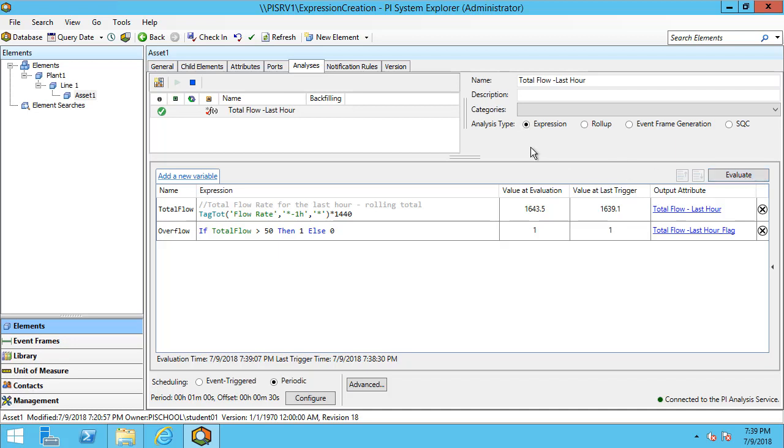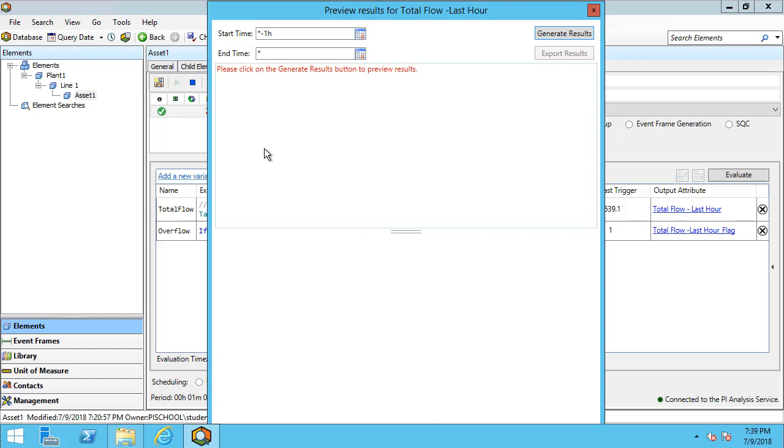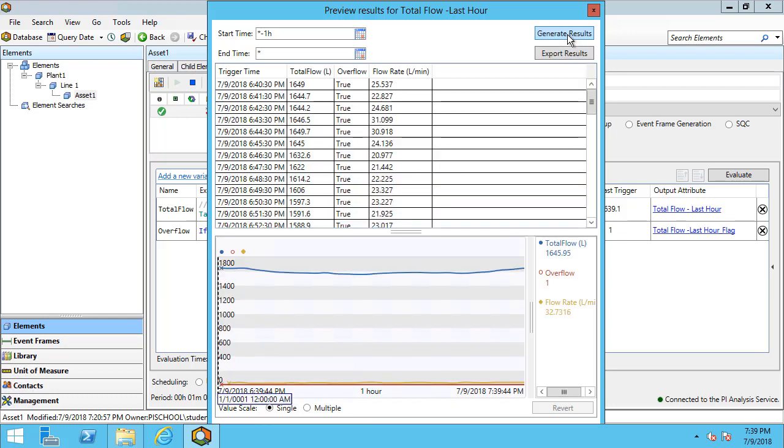The evaluate button will help you make sure that your results make sense. And if you want to see more detailed results, you can right click on the analysis and choose a preview results button. Here we're able to put in a time period. I'll take a look at the last hour and we can see the outputs as well as the inputs for the last hour at the time the analysis was run. We can see the trigger times are at 30 seconds past the minute and they're updating every single minute. And we can see what the flow rate attribute showed at that time, as well as the total flow attribute output. If we want to take a deeper look at these results, we can export them to a CSV file and view them in programs like Excel.